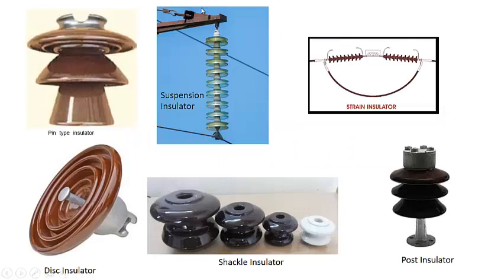This is the pin type insulator. These are known as petticoats. This is the groove in which the conductor will go from beneath, and a pin can be inserted into this, which is connected to the cross arm, and here we have to connect the conductor.